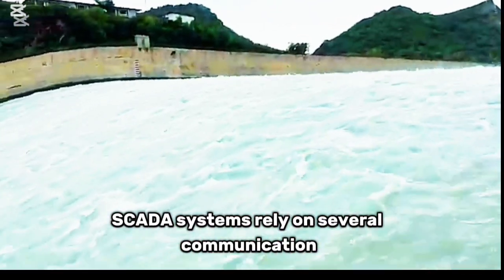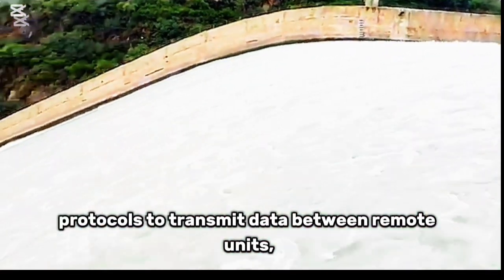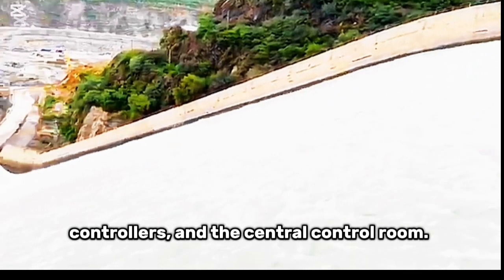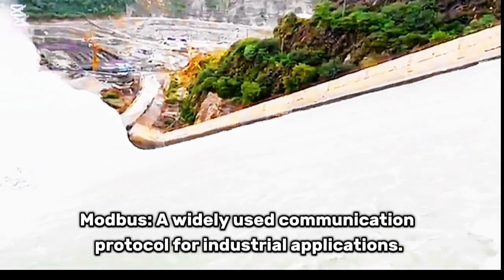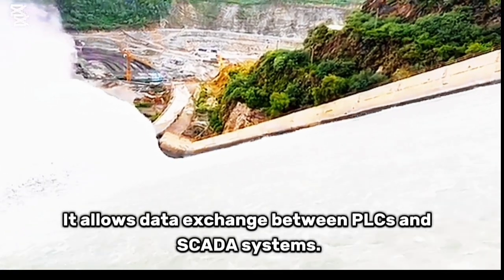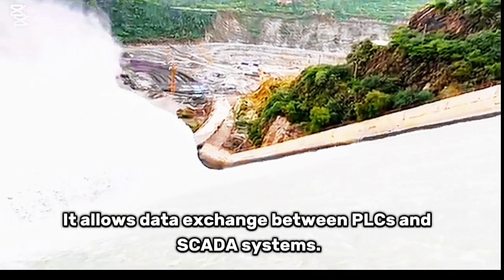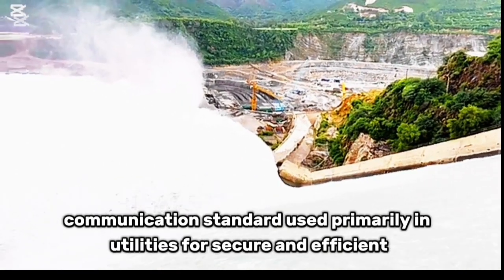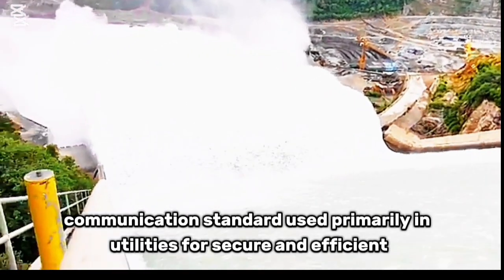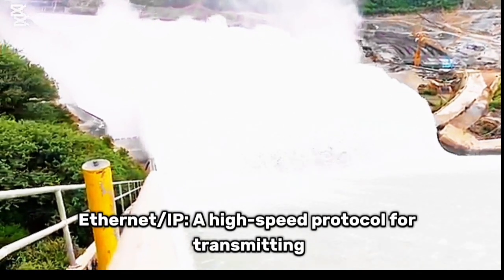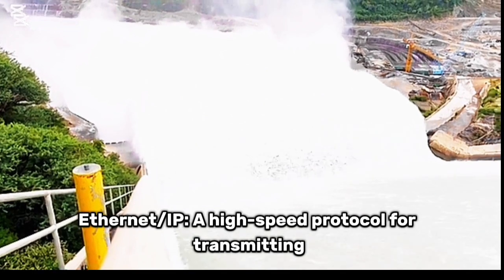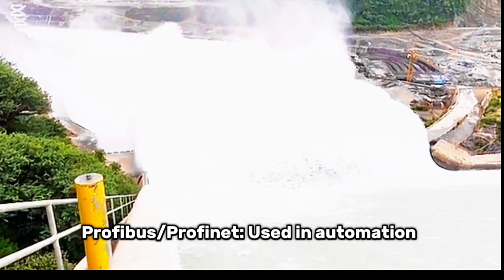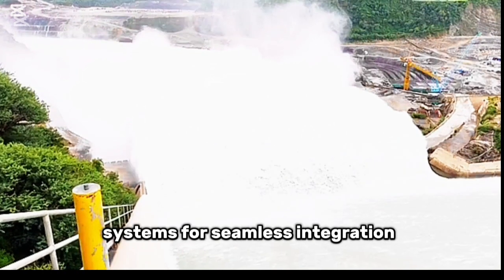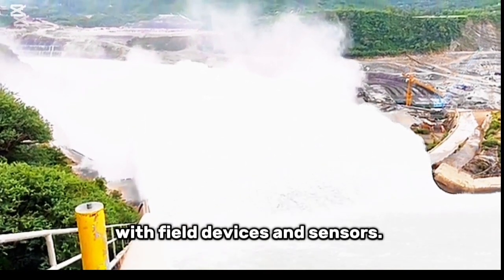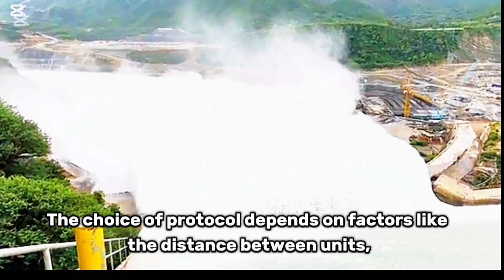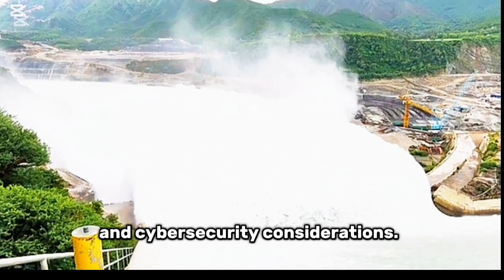SCADA systems rely on several communication protocols to transmit data between remote units, controllers, and the central control room. These include Modbus, a widely used communication protocol for industrial applications. It allows data exchange between PLCs and SCADA systems. DNP3, Distributed Network Protocol, a communication standard used primarily in utilities for secure and efficient data transfer. EtherNet/IP, a high-speed protocol for transmitting large volumes of data between devices. Profibus, Profinet, used in automation systems for seamless integration with field devices and sensors. The choice of protocol depends on factors like the distance between units, real-time performance requirements, and cybersecurity considerations.